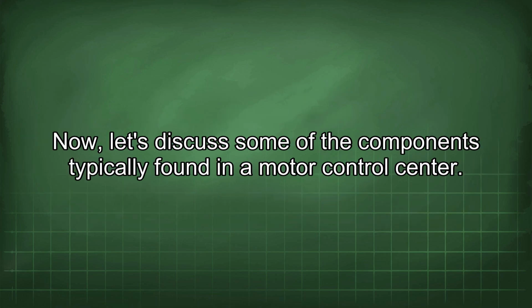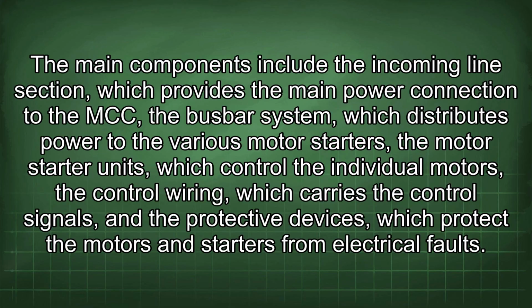Now let's discuss some of the components typically found in a motor control center. The main components include the incoming line section, which provides the main power connection to the MCC, the busbar system, which distributes power to the various motor starters, the motor starter units, which control the individual motors, the control wiring, which carries the control signals, and the protective devices, which protect the motors and starters from electrical faults.